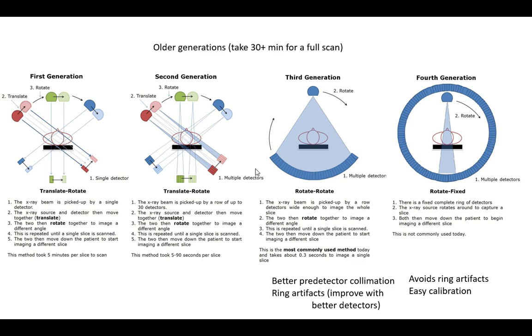All right, so let's just talk for a sec about 1st generation. The big reason we care about this is it's easy as pie. Remember what we said about that whole scanning situation, how do we get no artifacts, no scaling problems? I just take it and move it along, and then I move it down and repeat the same process, and so on. So in this case, I just scan all the way across, one at a time, just a single pair, rotate, and do the same thing.